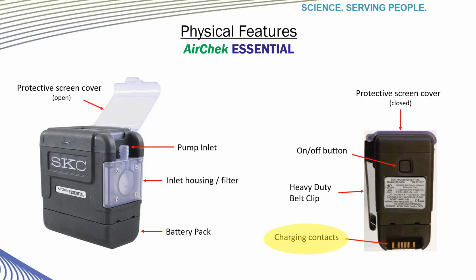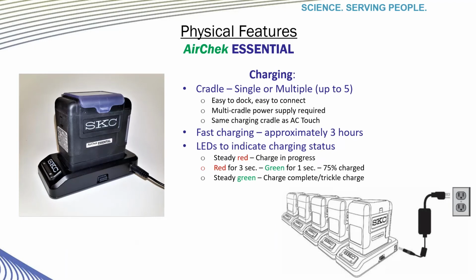Last is the charging contacts located and shielded at the bottom of the pump. This is another great advancement on this pump. It makes it very easy to charge. Instead of having to plug in a cord to each pump, you simply sit it or dock it into the cradle. You will see in the picture that the pump is docked in the cradle. The power cord is connected by a standard barrel connector fitting. Just to the left of where the power cord is connected to the cradle, you will see a little connection port that I've just highlighted.